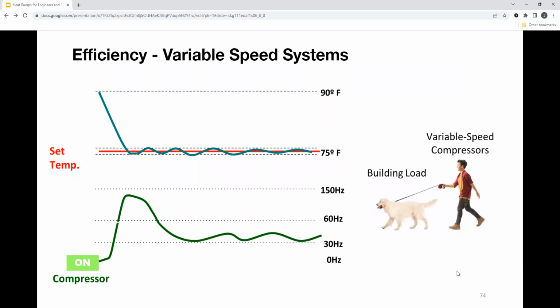And that's what your variable speed system is, right? Again, you have that set point, we're going down from 90 degrees. We're really ramping our compressor on. However, it does have a soft start on the compressor, which basically protects the compressor so it can last longer throughout the years. That turns on, ramps way up, trying to get to the set temperature as quick as possible. And then over time, we are reducing the energy and still keeping that temperature where we want it to be, right? The main thing I'm trying to get across is that on-off is not the way to go, and VRF and heat pumps in general are designed to be kept on, right? Because when it's kept on, we ramp the compressor down to a really low hertz, and that's what saves the electricity we're using, right?